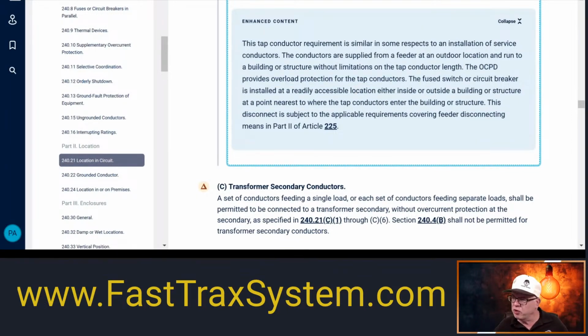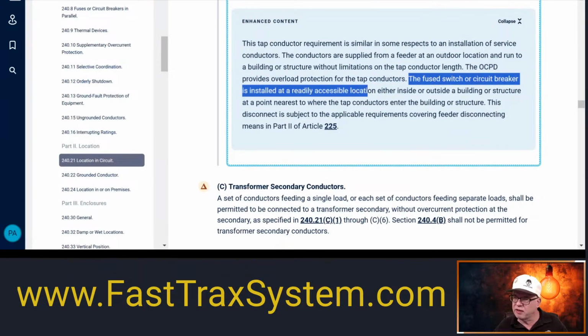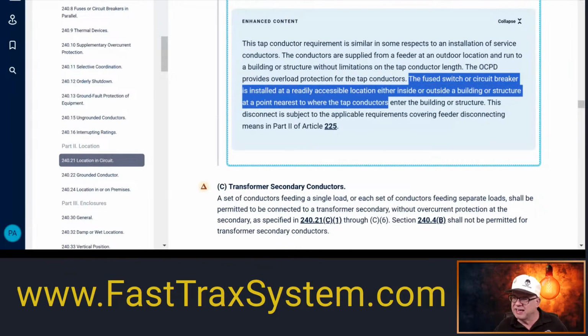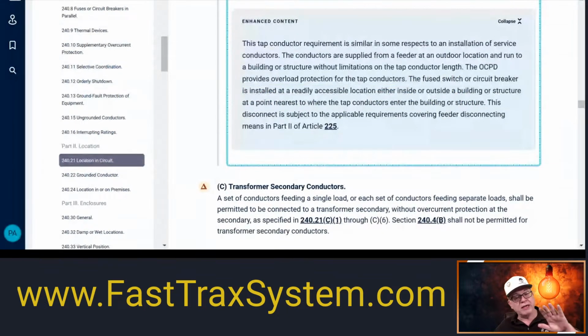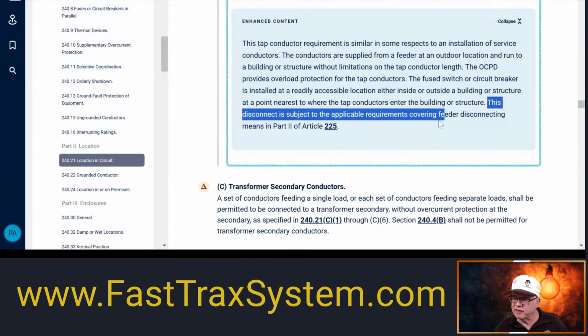It says the fuse switch or circuit breaker is installed in a readily accessible location, either inside or outside the building or structure, at the nearest point where the tap conductors enter the building or the structure, okay? If you want to do it outside or at the nearest point of entry. It says this disconnect is subject to the applicable requirements covered under feeder disconnecting means.